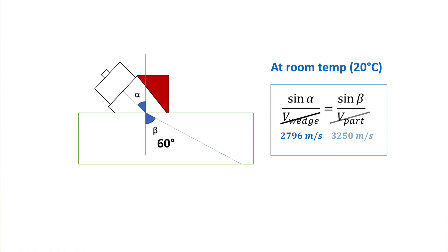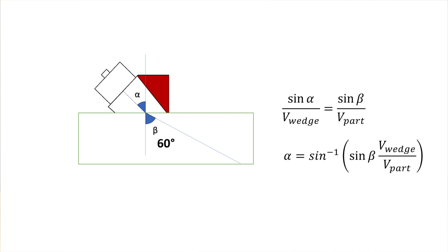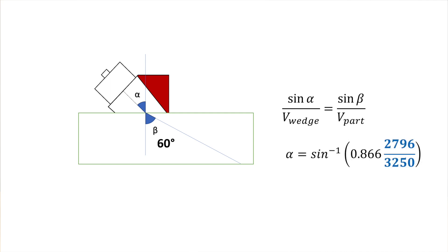The velocity of shear waves in steel is 3250. To solve for the angle of incidence of this wedge, we isolate alpha on the left-hand side, plug in those values for the velocities, and since the sine of 60 degrees is 0.866, alpha works out to be 48 degrees. We're going to take that cut angle of 48 degrees and use it to theoretically solve for the angle of refraction when we change temperature.